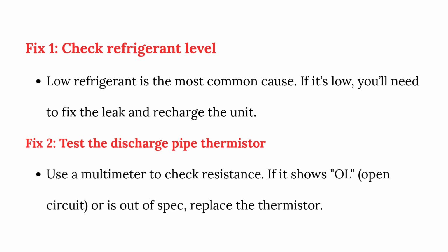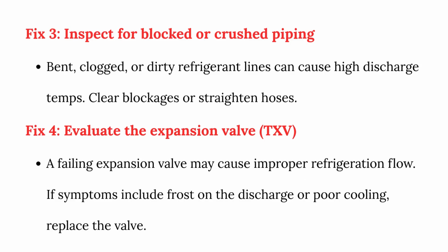Fix 2. Test the discharge pipe thermistor. Use a multimeter to check resistance. If it shows open circuit or is out of spec, replace the thermistor.